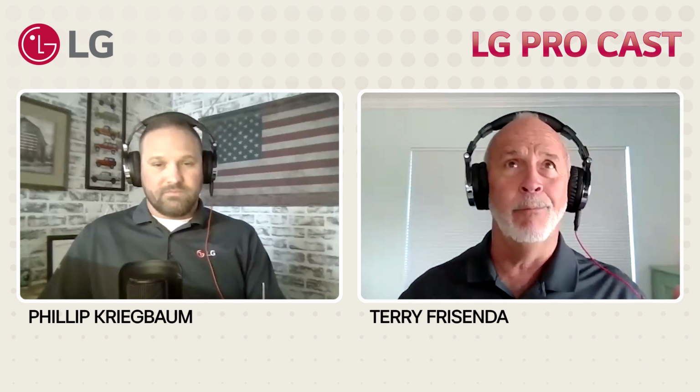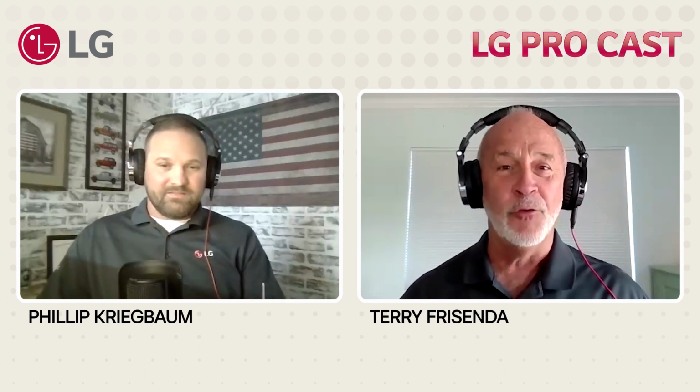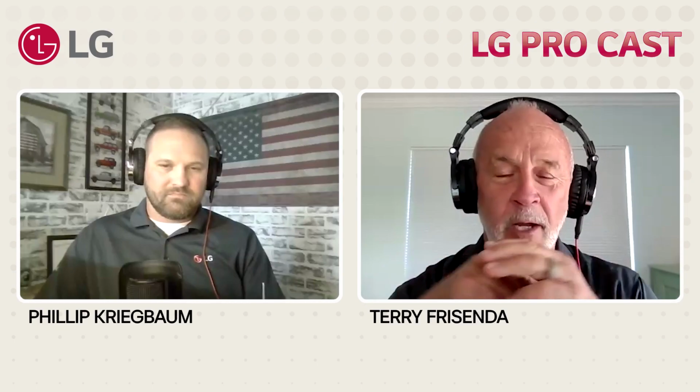Yeah. The whole mindset of kick the temperature up when you leave and kick it down and heat, cool, whatever. Man, if you just let this inverter get to temperature and maintain set point, it's using so much less electricity, and that's a really hard thing for folks to understand. I know, and in the inverter world that we work in, our fans run in the cooling mode 24/7 unless you disable it, which we have the capability to do. But then when you talk to folks, they think, oh, that's using so much power, and really, I did it for an exercise when I was new here. A 40-watt refrigerator light bulb, or that little 16-watt light bulb, uses more electricity in a month than my little fan motor did in a month, based off the kW rates where I was doing the example. And so they're like, okay, I get it. It doesn't use any power.